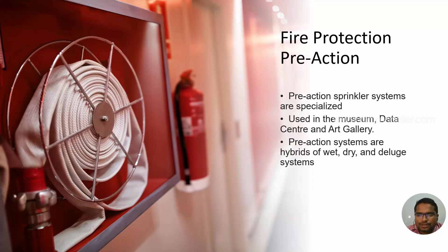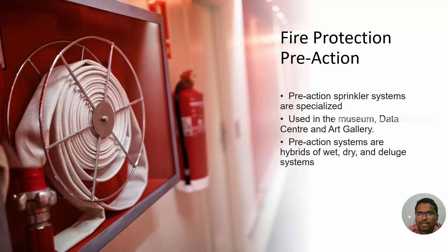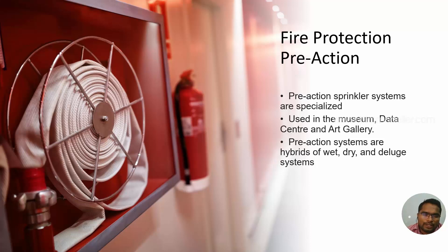Fire protection pre-action. This is a pre-action sprinkler system specially designed and used in museums, data centers, and galleries — places more affected by water where we cannot use a wet or dry system. We have to use a specialized system. The fire should be detected first before releasing water to the system. This is a combination of wet, dry, and deluge systems. Water will not be present in the pipes, and the fire alarm and electrical system will detect the fire condition.